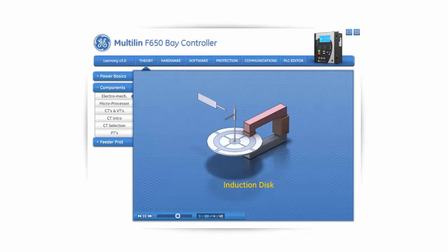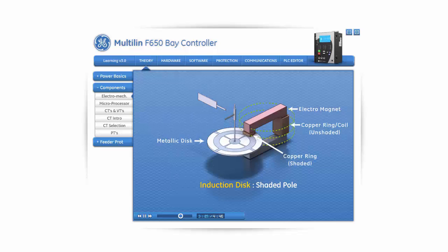The induction disc element consists of a metallic disc of copper or aluminum, which rotates between the pole faces of an electromagnet. There are two styles of induction disc, the shaded pole style and the watt-metric style, each having its own principles of operation. In the shaded pole style, a portion of the electromagnet pole face is short-circuited by a copper ring or coil, which causes the flux in the shaded section to lag the flux in the unshaded section.